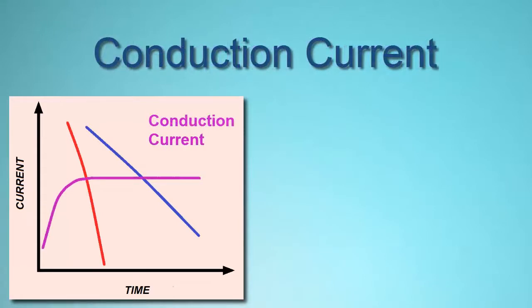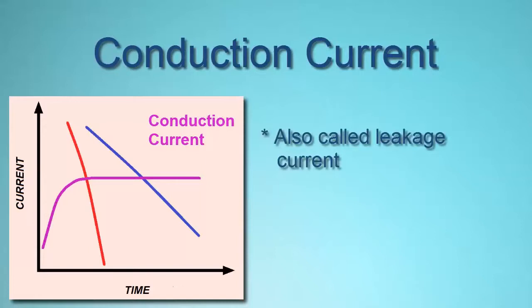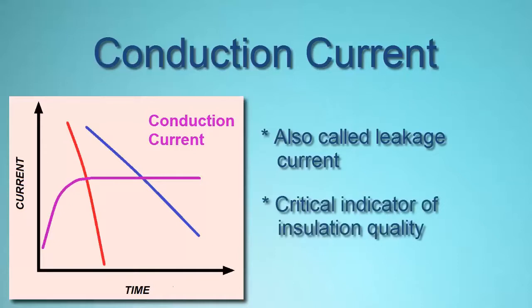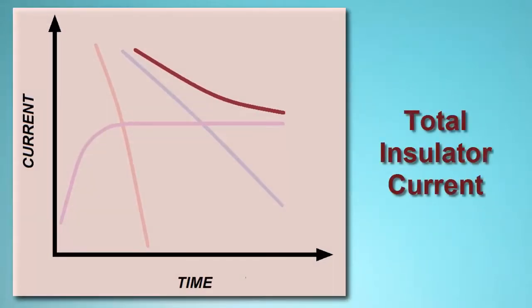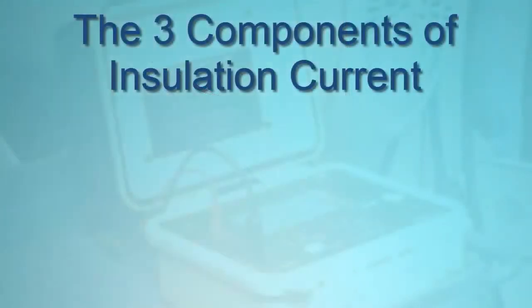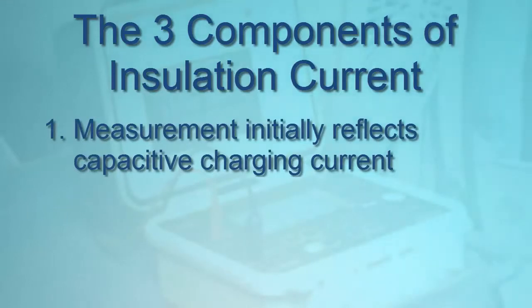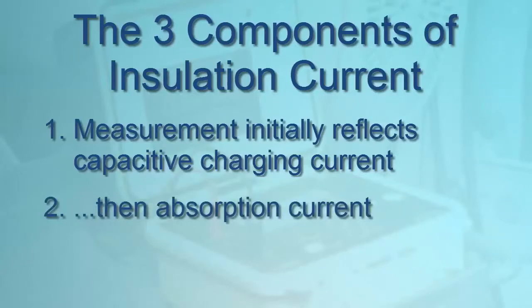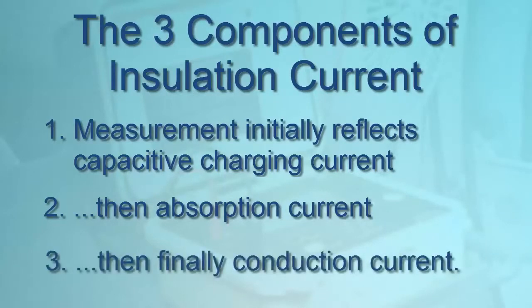Conduction current, often called leakage current, is the steady current present both through and over the insulation. This is a critical measurement, since an increase in conduction current over time is likely an indication of deteriorating or damaged insulation. Combining these three components produces a total insulation current profile similar to the illustration shown on the screen. For a typical test, the initial measurement primarily reflects capacitive charging current. After a period of time, absorption current is dominant. Beyond 1 to 10 minutes, the measurement is mainly composed of conduction current — the primary value used to calculate the quality of insulation resistance.